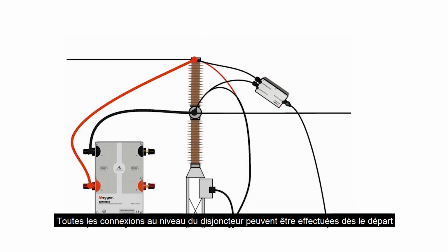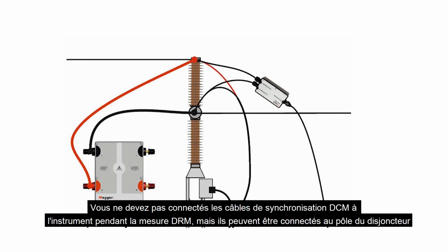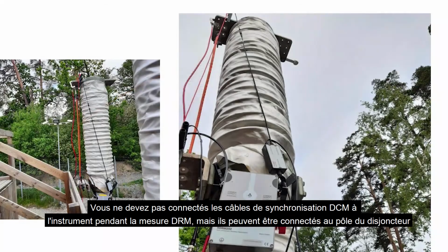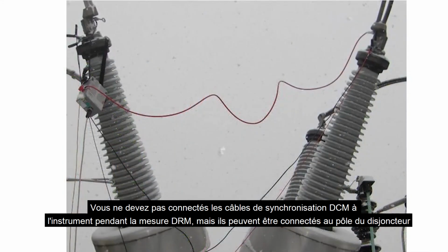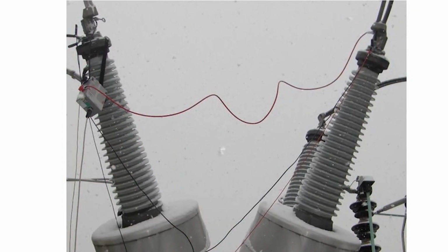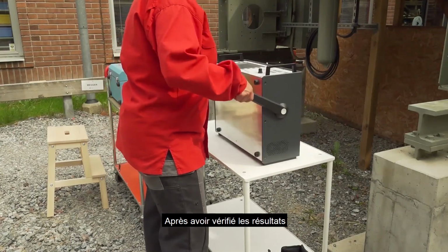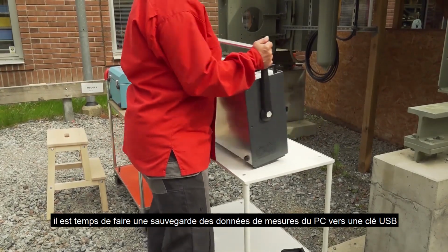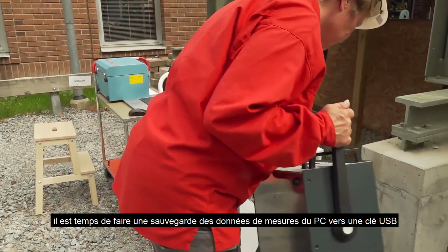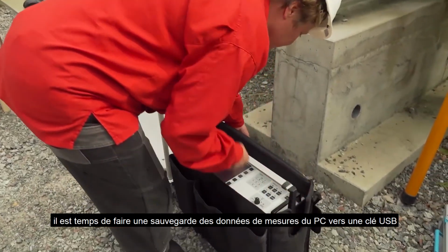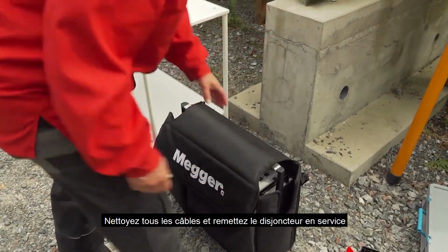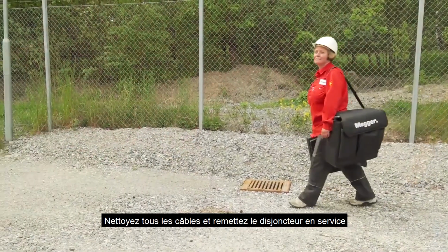All the connections at the circuit breaker can be done from start. You don't have the DCM timing leads connected at instrument during the DRM measurement, but they can be connected at the pole of the breaker. After checking the result, it's time to do backup of the results of the data from the PC to a USB memory. Clean up all the cables and put the circuit breaker back into service again.